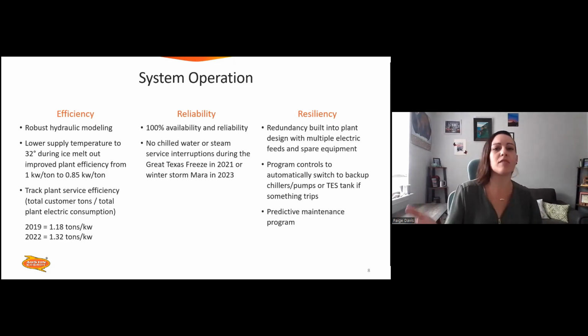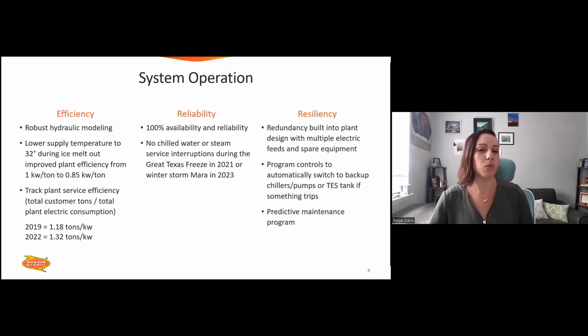And resiliency, I talked about how we make sure that's built into our plant design from the beginning, with things like redundant equipment. We also always make sure we have multiple electric feeds into all of our plants, so in case we lose one feed, we're able to power the plant from another feed. We also have programmed the controls in the plants so that they're able to automatically switch to either backup chillers or the thermal energy storage tank if something trips. So if something happens to a chiller, the control system will take it offline and switch to a backup chiller, which we always have available, or if we're running peak, we do have the thermal energy storage as a backup.